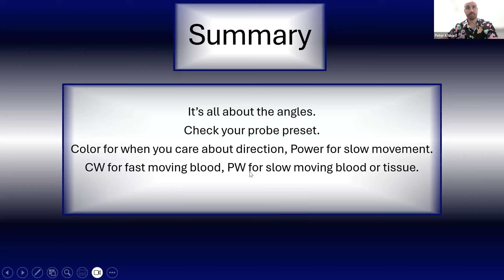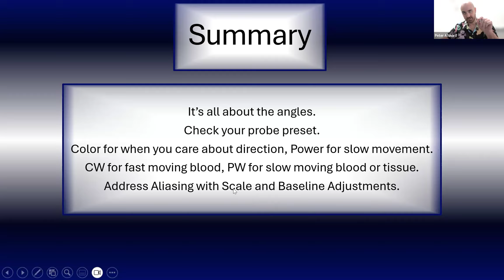You're using color Doppler for when you care about the direction, and then you're using power Doppler when you have little, small movement things where the direction isn't as important. And then similarly, using continuous wave Doppler for things that are moving really fast, and pulse wave Doppler where you have things that are moving slow, but you need to know what the direction of the flow is. And you can address aliasing using adjustments to the scale on the machine and moving the baseline. The scale has to be adjusted while the machine's shooting sound waves out, but the baseline can be changed afterwards.